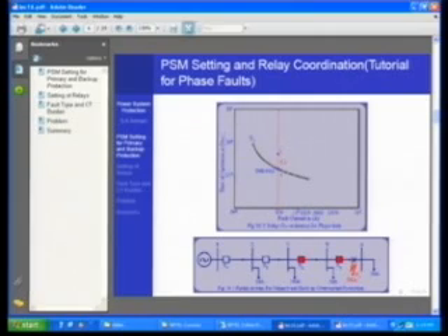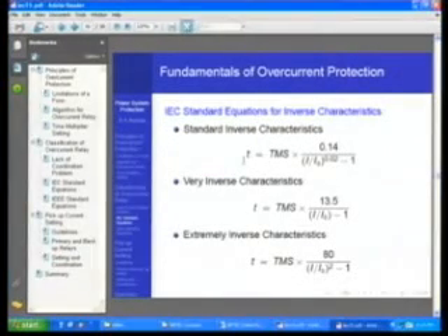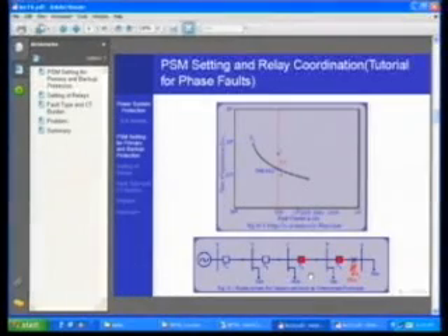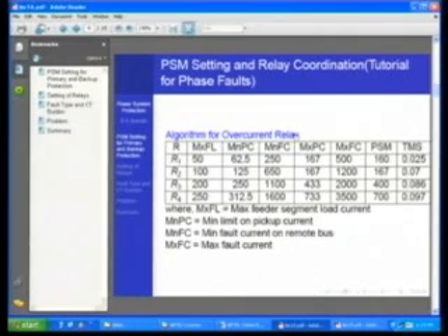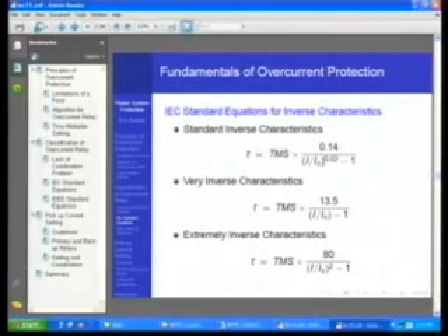That is the time for the relay to operate. So this time for the relay to operate is now known. The pickup value has been calculated here. This is not the PSM, this is actually the pickup value. The pickup value has been already calculated here. So you know the pickup value, which is IS, you know the operating time of the relay. There is only one unknown, so you just solve that equation and calculate the TMS value.